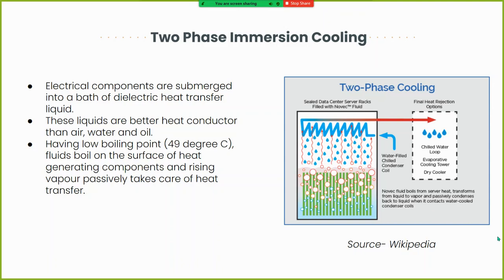A little about the two-phase immersion cooling system: electrical components are submerged into a bath of dielectric heat transfer liquid. As you can see in the image, the green figures are the components submerged into the liquid. These liquids generally have a low boiling point, and the vapor subsequently generated due to the heat of the components passively takes care of the heat transfer.